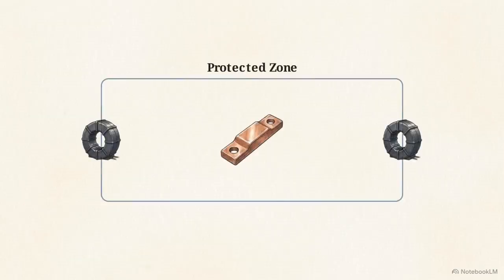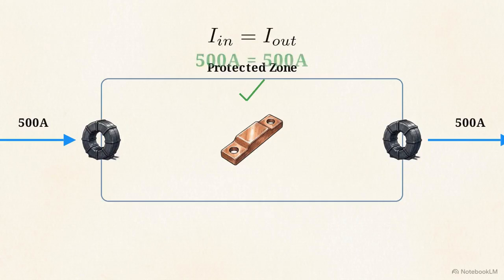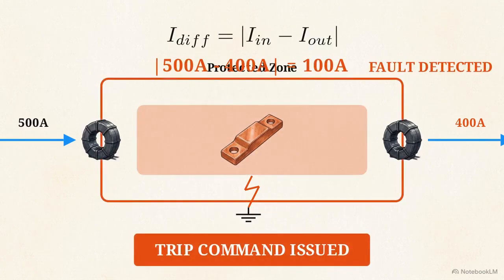Phase A focuses on differential protection, designated as Relay 87. These modules operate on Kirchhoff's current law, which requires that the current entering a healthy zone must precisely equal the current leaving it. Any missing current indicates an internal fault leaking to ground.